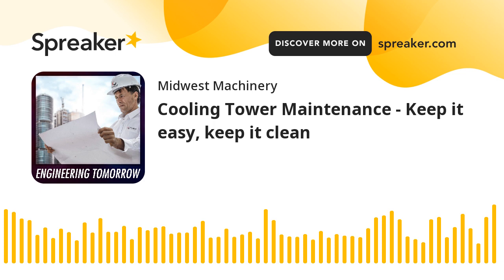There's a common misconception that cooling towers cause Legionella. A lot of people don't know that water from your municipalities is not 100% sterile. There are actually small trace amounts of bacteria that come from the municipality. By the time it gets through miles of pipes into your building, you get a couple strands of bacteria. They latch onto a wall in the pipes, and then they multiply. Once they get to a certain size, some of that bacteria breaks off and moves farther down your system, gets to your tower, and multiplies even more. But the tower itself is not the cause of Legionella, it's just someplace that Legionella can live.